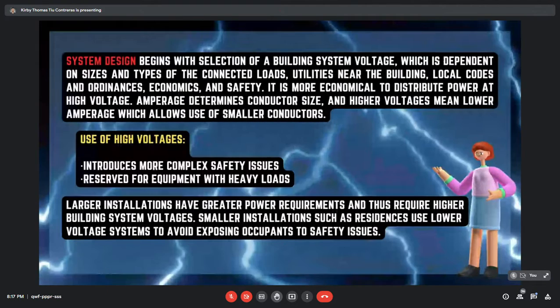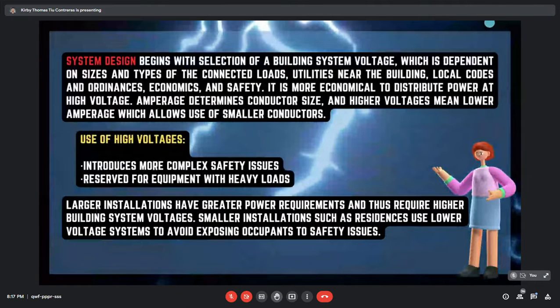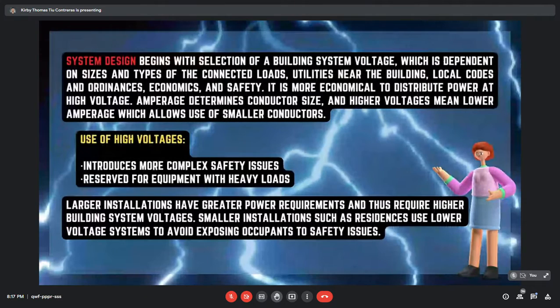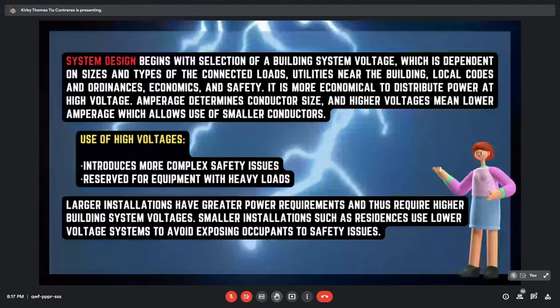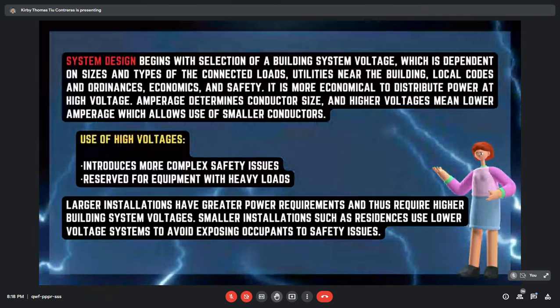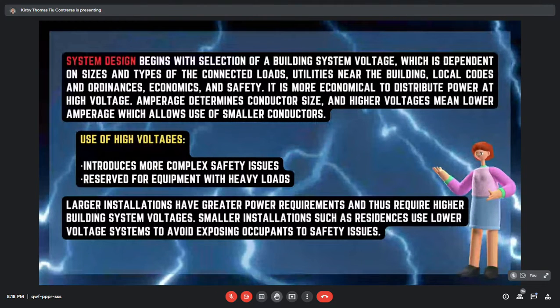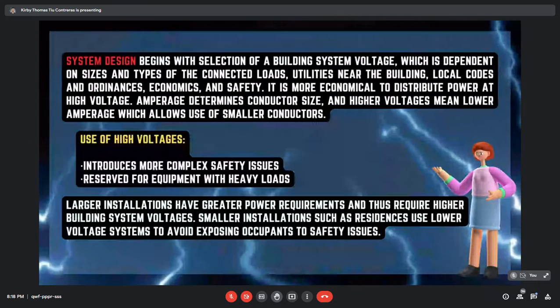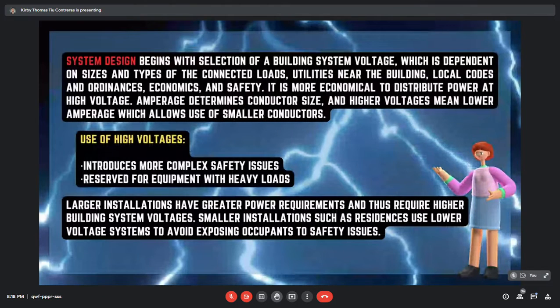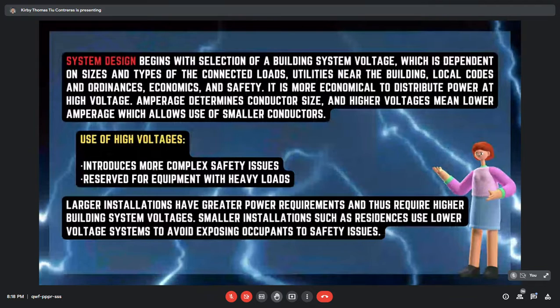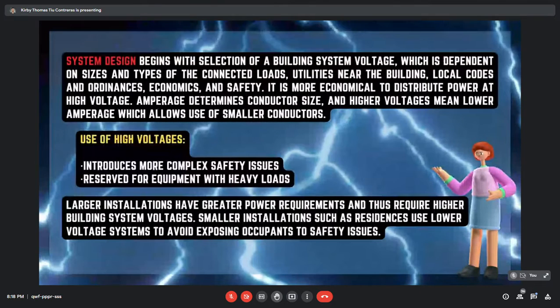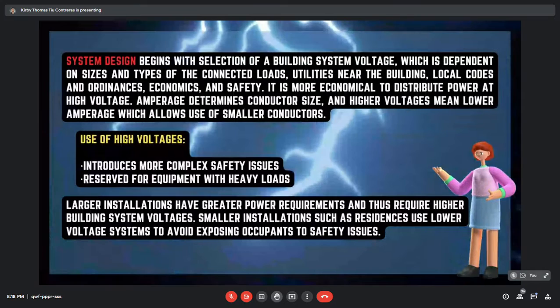They are needed to operate our heaters, fans, and elevators. There are many possible electrical systems that can be used to distribute power in a building. Typically, system design begins with the selection of a building system voltage, which depends on the sizes and types of the connected loads, utilities near the building, local codes and ordinances, economics, and safety. It is said that it is more economical to distribute power at high voltage because it is more efficient than a lower voltage, since it experiences less energy loss from resistance.